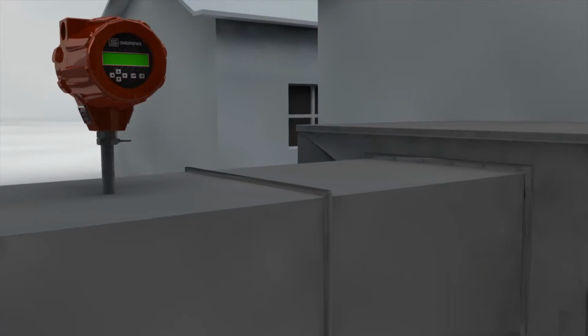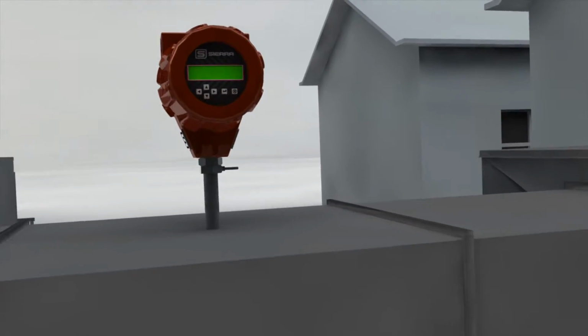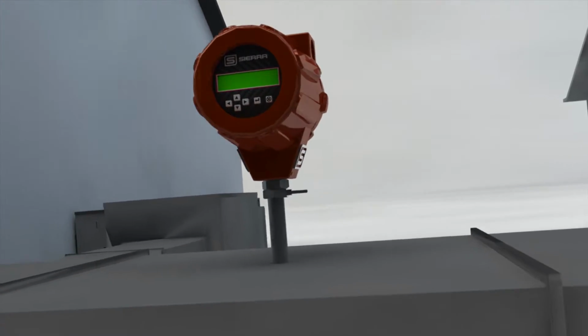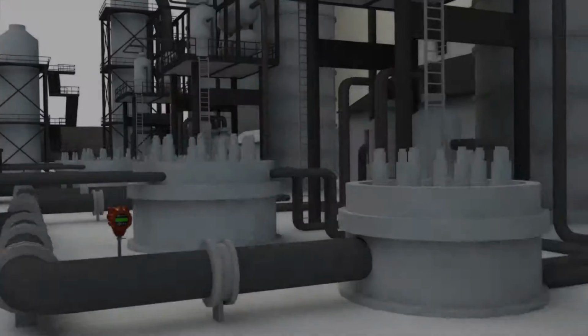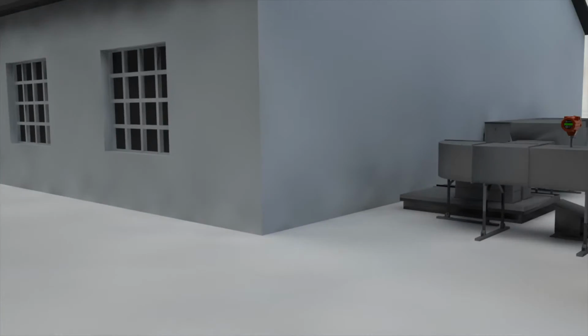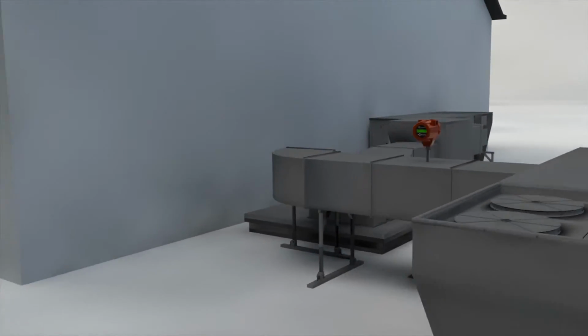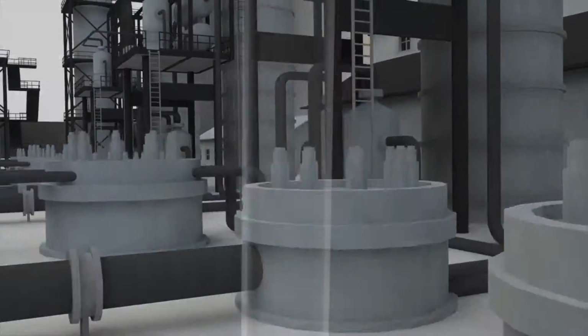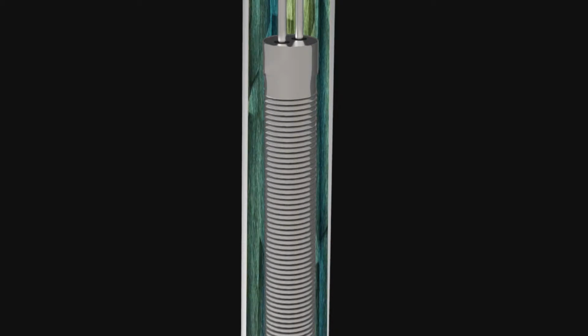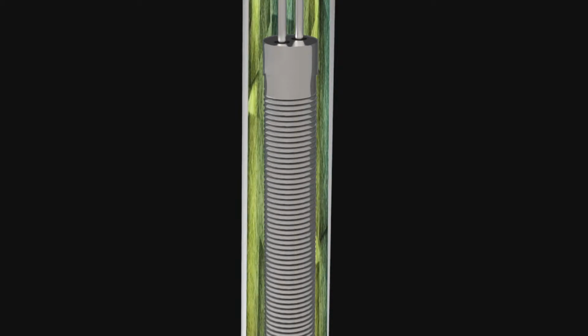Industrial thermal mass flow meters comprise a family of instruments for precision measurement of total mass flow rate of gases in the pipes and ducts. So, when evaluating thermal mass flow meters for in-situ calibration validation capability, be aware that sensor drift will create false positives, reducing the reliability of the validation.